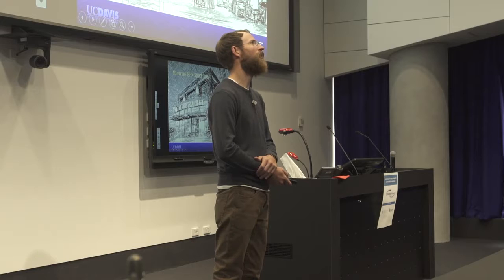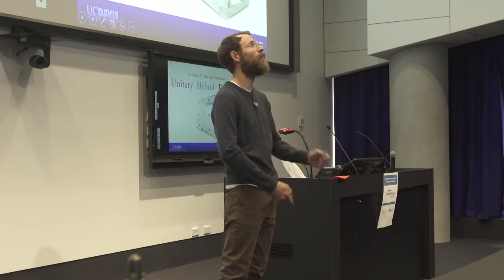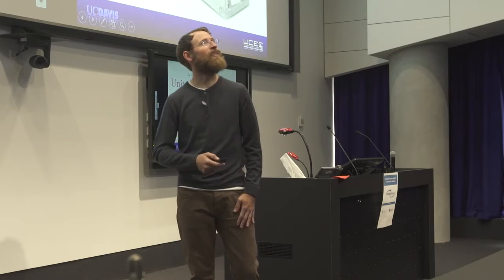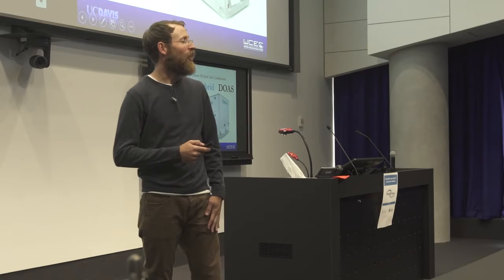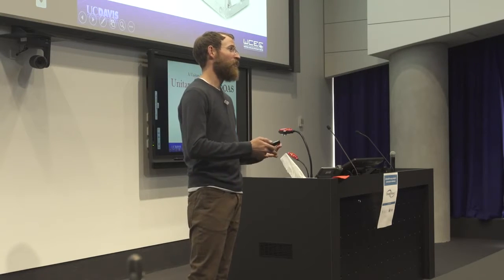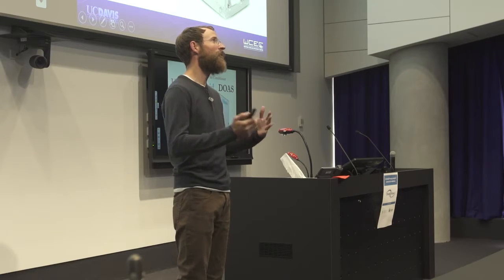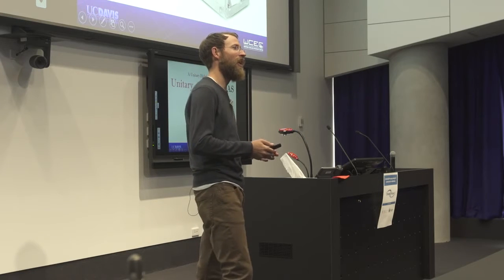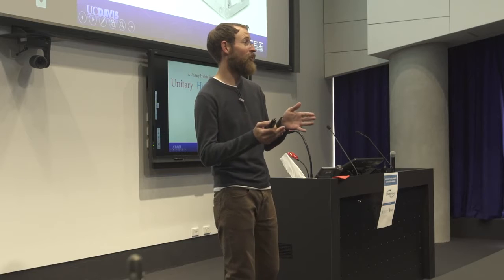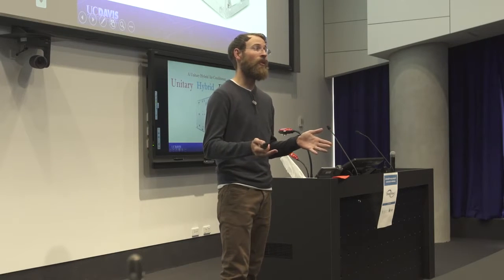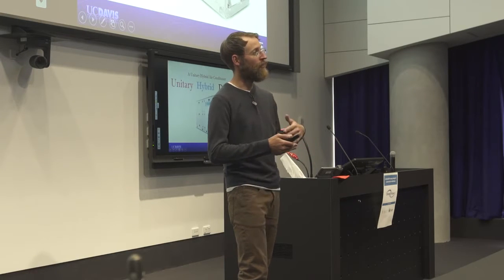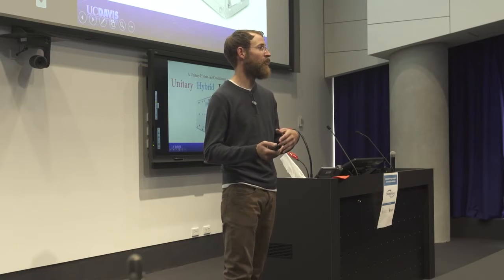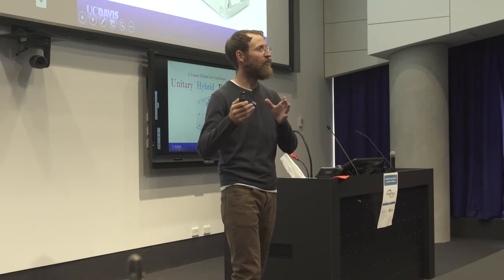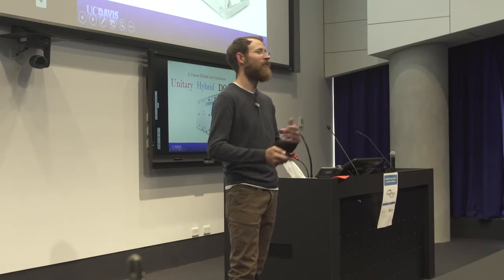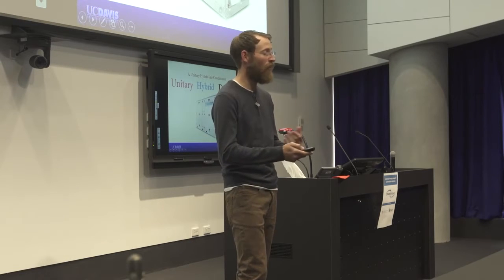We ran a laboratory test of their equipment and then subsequently ran through a field evaluation in collaboration with a Whole Foods market in California. One of the exciting parts about the system is that I call it a hybrid because it uses indirect evaporative together with vapor compression, but it's a whole packaged unitary system that's designed as a dedicated outside air supply. So it incorporates the vapor compression together with indirect evaporative cooling in the same unit, whereas all those other examples that I showed were as retrofit additions to existing rooftop packaged air conditioners, and some of the other installations we've done use indirect evaporative cooling in sort of parallel in the same building as an existing packaged air conditioner. Well, here they put it together all in one box.